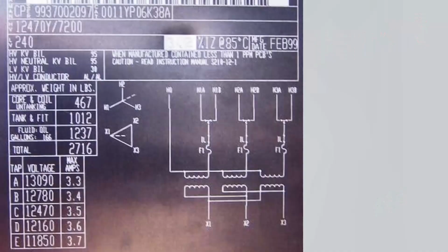So let's look at this one right here. This is a YD, all right? And if you've noticed, I haven't used the square root of 3 on any of these numbers yet, okay? There's only one time when you really need to start pulling out stuff and it gets a little squirrely. That's if you don't have this neutral, and then you have to do a phase-to-phase value on the Y, all right?